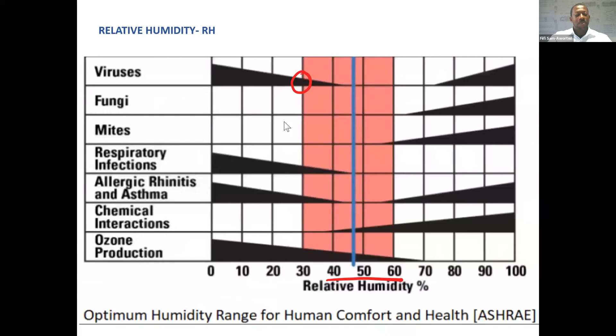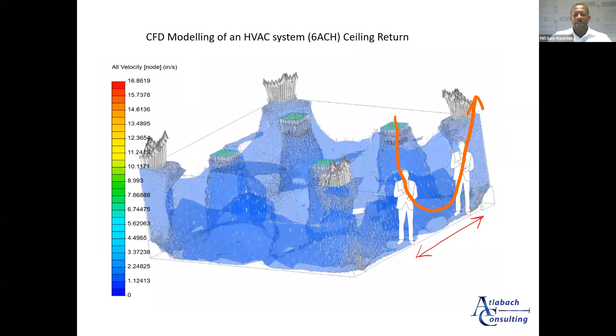So now we go to computational fluid dynamic modeling, CFD modeling. This is used to simulate or check airflow patterns to ensure there is even distribution. In an airborne infectious isolation room, we would be looking at virus transmission patterns and control. As shown in the model on the screen, we have the air coming from the top and the return or exhaust also at the top. So the airflow pattern is from the top, hits the ground, and is sucked up through the return or exhaust. So in the event of an infected person standing under the supply and a healthy person under the return, contaminated air will be swept to the healthy person, even though he might be 6 feet away, observing social distancing. So it's important to understand airflow patterns in hospital environments.